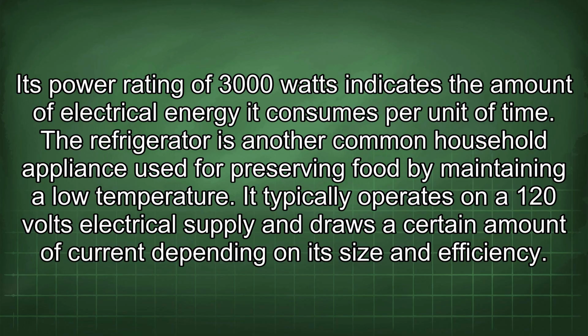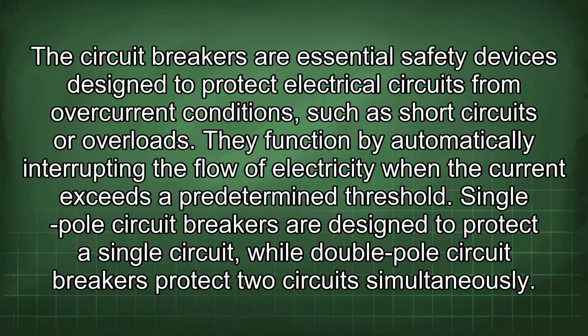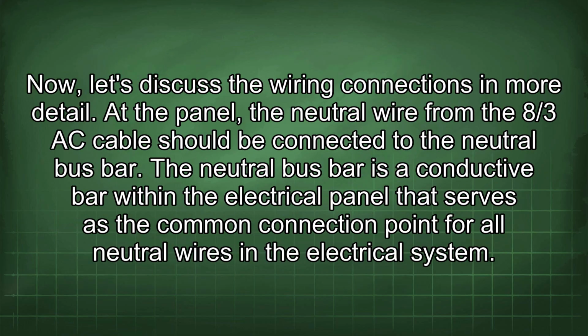draws a certain amount of current depending on its size and efficiency. The circuit breakers are essential safety devices designed to protect electrical circuits from overcurrent conditions, such as short circuits or overloads. They function by automatically interrupting the flow of electricity when the current exceeds a predetermined threshold. Single-pole circuit breakers are designed to protect a single circuit, while double-pole circuit breakers protect two circuits simultaneously. Now, let's discuss the wiring connections in more detail.